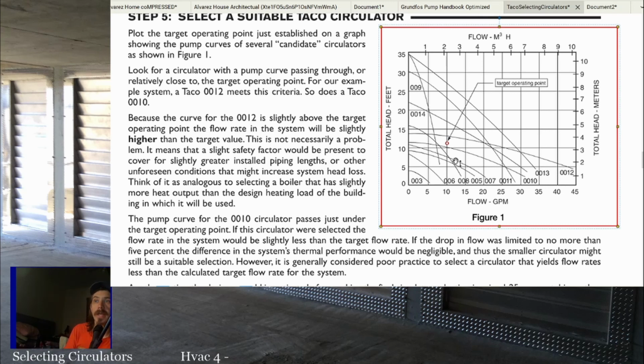So you want something that operates very close to where you want it, because this is the operating curve for the pump, right? It's going to be hard to get this pump to pump exactly where you want it because that's not on the pump curve. So you try and get one as close as possible to the pump curve. And we'll look here at 0012, right? Is very close to the operating point. And a 0010 is pretty close to the operating point.